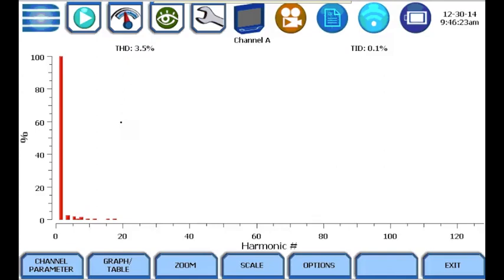The harmonic graph shows each individual harmonic with an order up to 127 for voltage and 63 for current. Each individual harmonic can be displayed as a frequency or by harmonic order number. The magnitude of each harmonic can be displayed as volts, amps, watts, or as a percent of its fundamental as shown on this display.